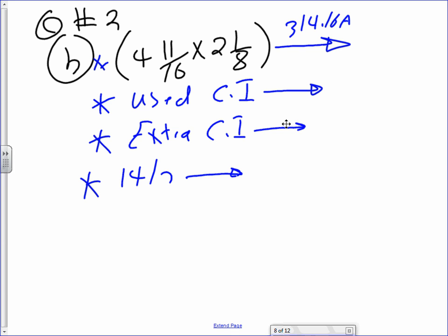Now, remember, we sized the box. Now I'm asking you for B: how many extra number 14/2, not 12/2, can you pull into this box? The way you're going to do it, guys, is first find the cubic inches for the box that you filled.